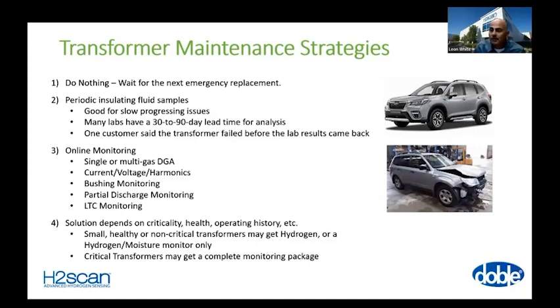What a lot of people like to do from a maintenance strategy is the do nothing strategy. There's lots of people that see transformers out there as a big gray box, and as long as it keeps humming, there's no issues. They really do not understand the complexities involved in that piece of equipment, and there's usually a lot of other things going on. If you work for a utility, there's trees to be trimmed, there's lines to be built, there's storms coming through.